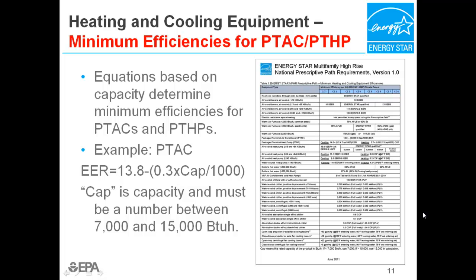Minimum efficiencies for packaged terminal air conditioners and packaged terminal heat pumps are determined using capacity-based equations. For example, the minimum energy efficiency rating for a PTAC is determined using this formula. If the proposed PTAC is less than 7,000 BTUs per hour, 7,000 must be used in the equation. Similarly, if the proposed PTAC is greater than 15,000 BTUs per hour, 15,000 must be used in the equation. At a capacity of 12,000, this formula yields a minimum EER of 10.2 as a prescriptive requirement for a PTAC.